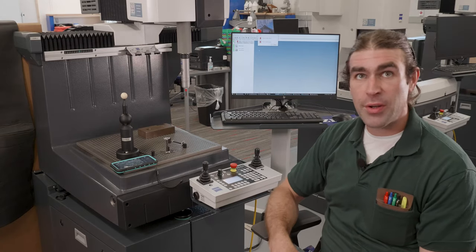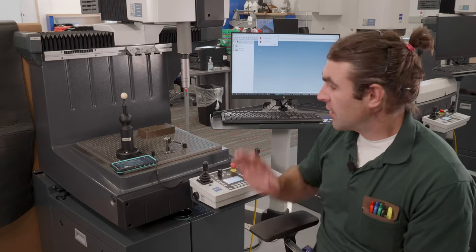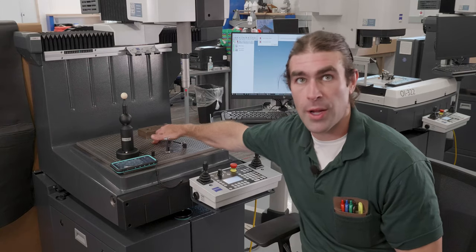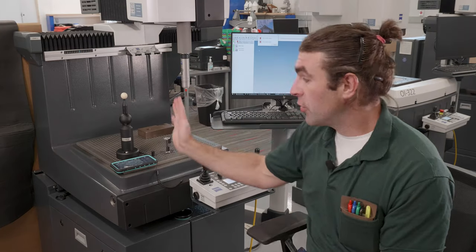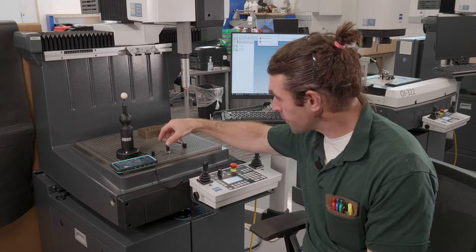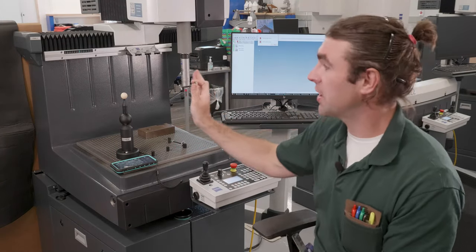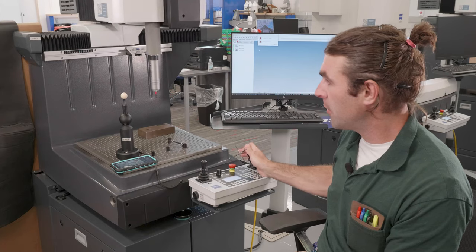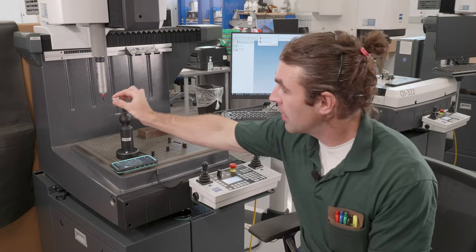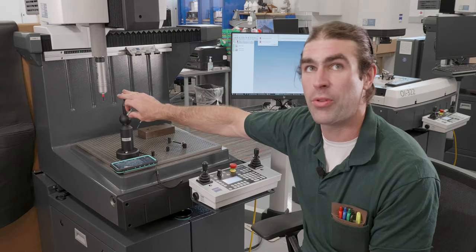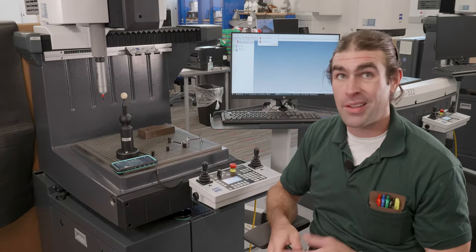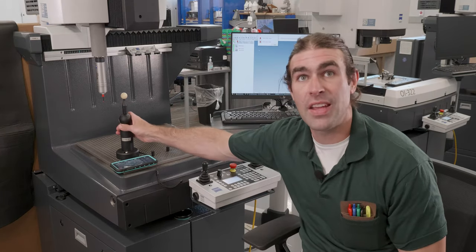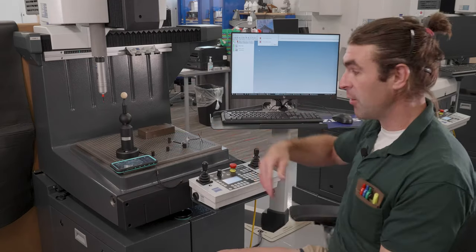Now we're ready for step two. We're going to mount the reference sphere. You can put it anywhere you want. The only criteria is that you don't really want to put it in the middle because it's probably where you're going to put your parts. You can run the risk of running the machine into the reference sphere, which we don't want. You can put it near the edge, but you don't want it hanging off of the edge in case you're qualifying a star probe. The machine can only go so far out. So what I'll typically do is drive the machine over, see how far it can go. I'll grab the biggest star probe I'm going to use and make sure I still have room for the reference sphere before I go ahead and bolt it down. You can use bolts, clamps, or even crazy glue. Anything that's going to get this thing on the table where it won't mysteriously move around.